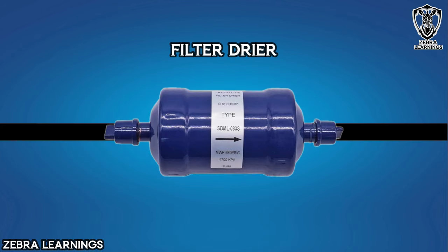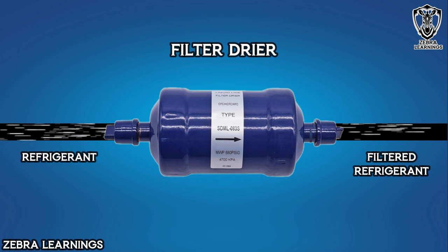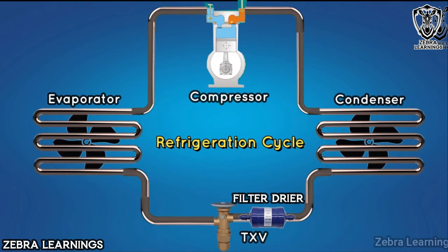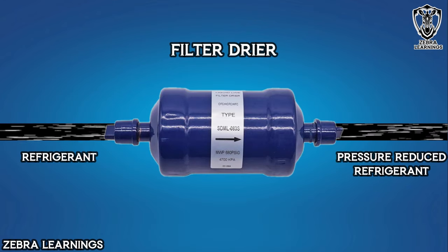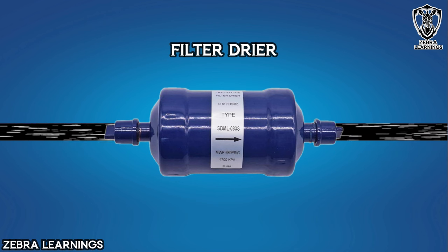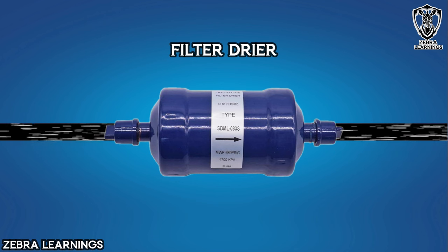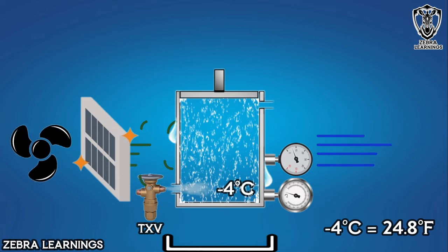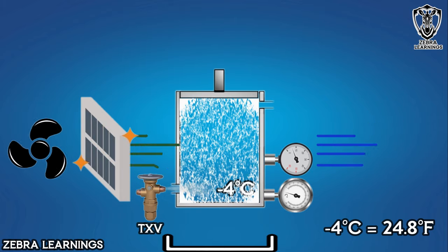Finally, the filter dryer can also be a cause of this problem. The important job of the filter dryer is to filter the refrigerant flowing in the AC unit. This filter dryer is located between the condenser and the expansion valve. If the filter dryer is blocked, the refrigerant passing through it will not be able to escape completely, but only a small amount will escape. Due to this, the refrigerant goes to the evaporator coil in less amount. So, the pressure of the refrigerant decreases and the temperature in the evaporator coil goes to freezing point.